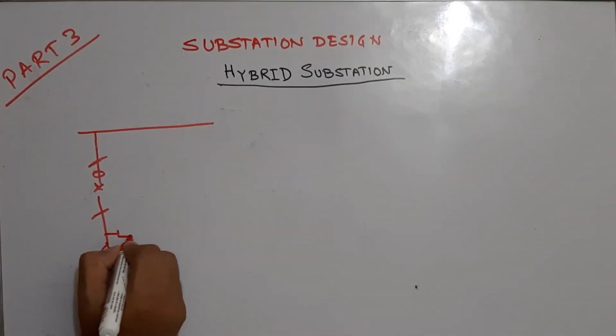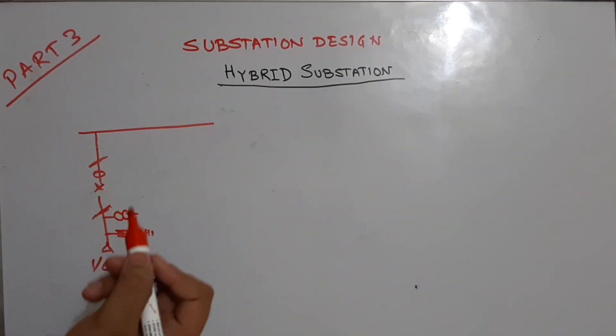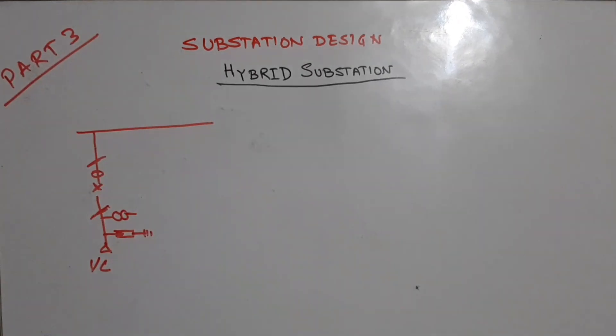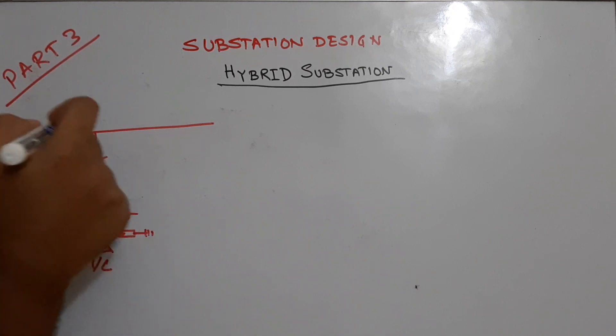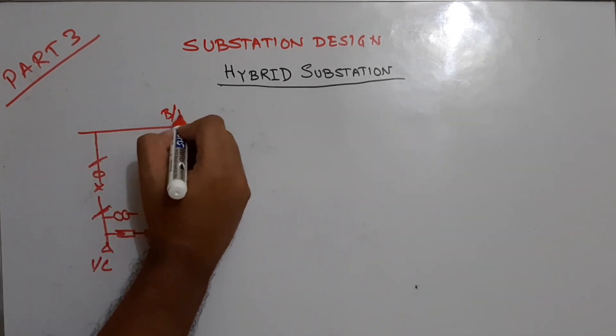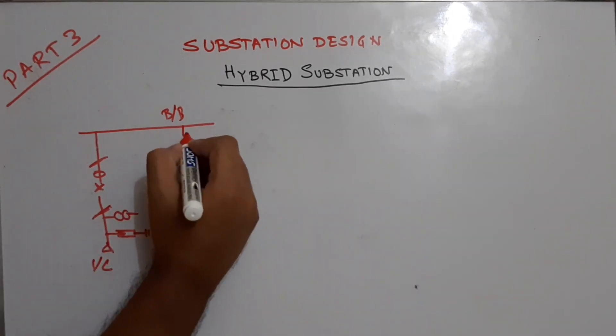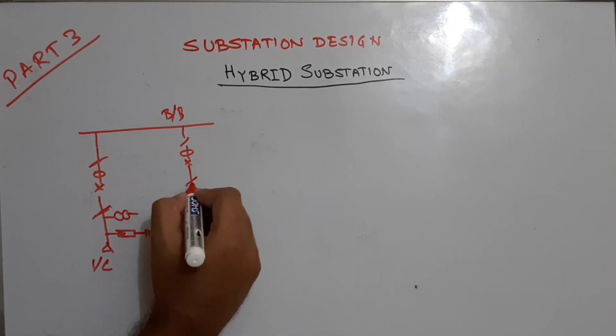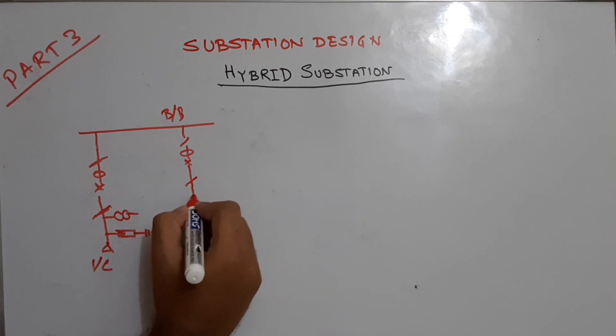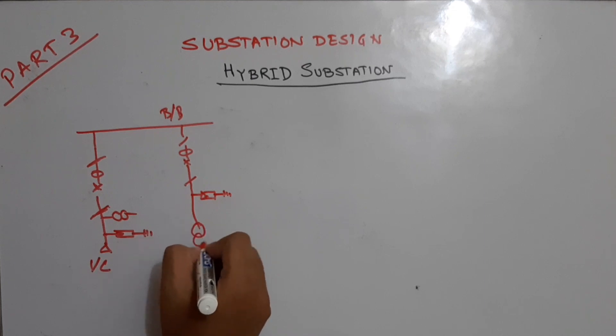For the incoming feeder there is a lightning arrester and a line PT. So the incoming feeder sequence is: lightning arrester, line PT, isolator, circuit breaker, CT, isolator, then connected to the main bus bar. For the outgoing transformer feeder the arrangement is: isolator, circuit breaker, CT, isolator, then a lightning arrester and the transformer.